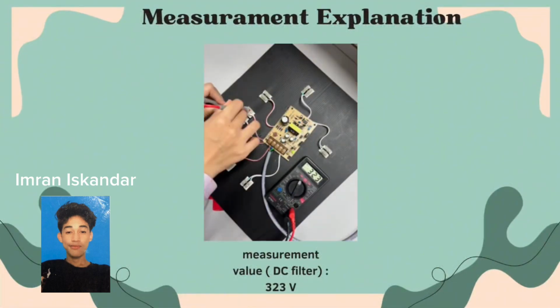So moving on to the next one, which is the primary rectifier. We need to switch our multimeter into DC voltage mode and place the probe across the positive and negative terminal of the rectifier. The expected reading is a DC voltage slightly higher than the peak AC input voltage, around 310 volt. During the measurement, we got the DC filter voltage value, which is 323 volt.